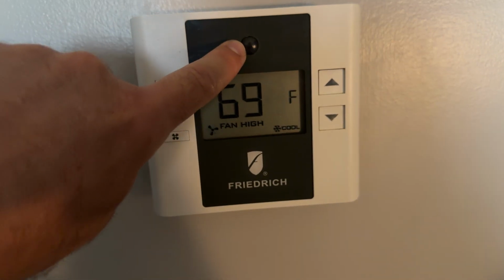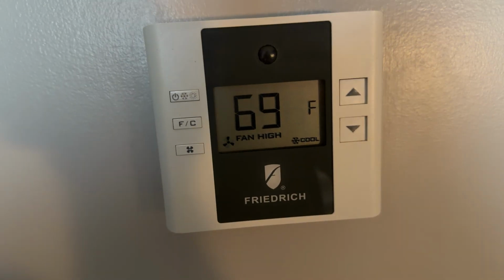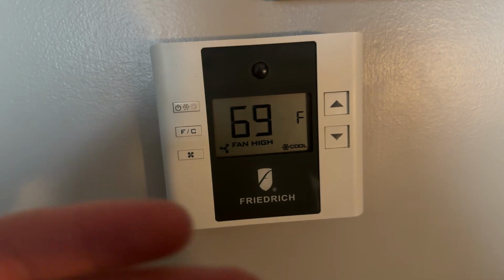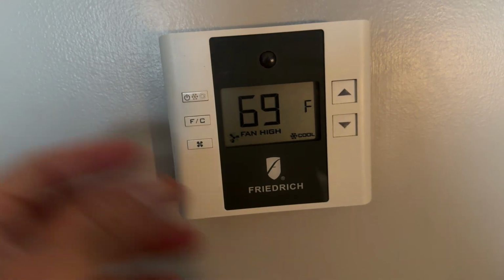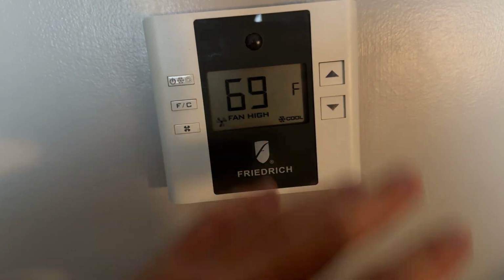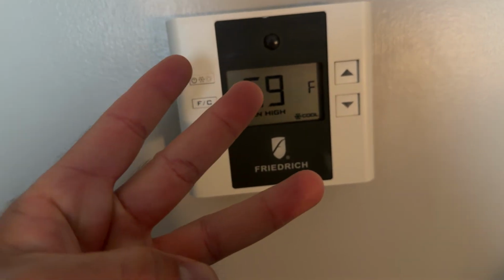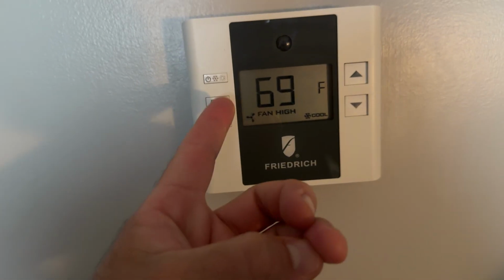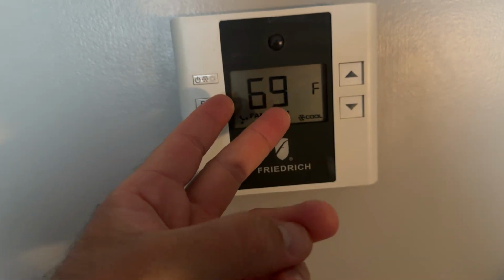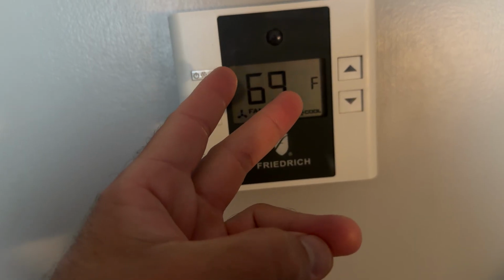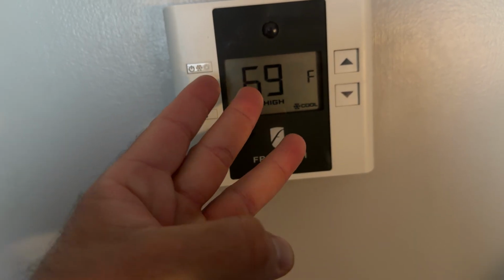So sometimes at night, after it doesn't sense any movement, it'll say, oh, the room is unoccupied, and go back to its set point automatically, even though you've fixed the temperature. So there's three different things going on. Constant fan, the lowest, or changing the temperature range that the guest can input, and getting rid of that setback because of the sensor.